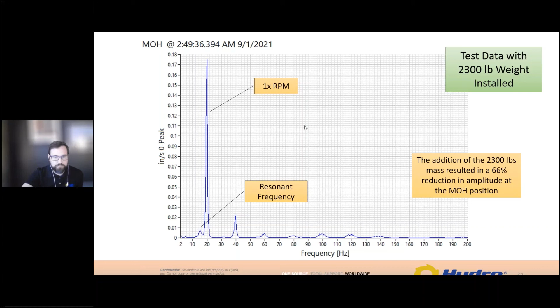The thing I would caution you is that you ignore it at your peril. The vibrations that you can get due to resonance are extremely high. In that installation, the A and B pump were fine. The C pump was being excited. The suspicion is that there's been some structural degradation at that one, so it has lost some stiffness over time, and its natural frequencies have come into resonance. If you want an engineered approach to the solution, that is something you can do with this modal analysis, finite element analysis type of technique.